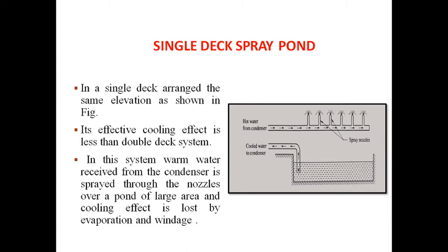Single deck spray pond. In this system, spray nozzles are arranged at the same elevation as shown in the figure. Its effective cooling effect is lesser than the double deck system. In this system, warm water received from the condenser is sprayed through the nozzles over a pond of large area, and the cooling effect is lost by evaporation and windage.